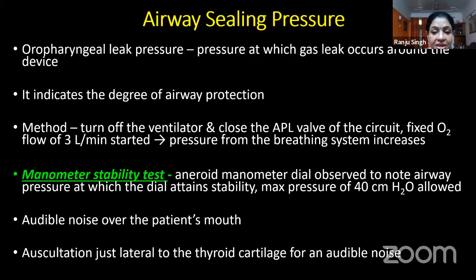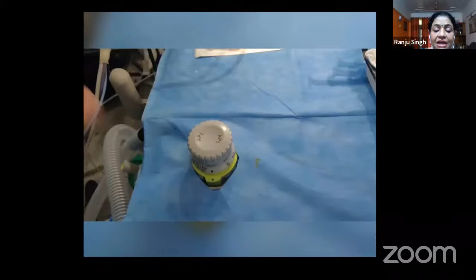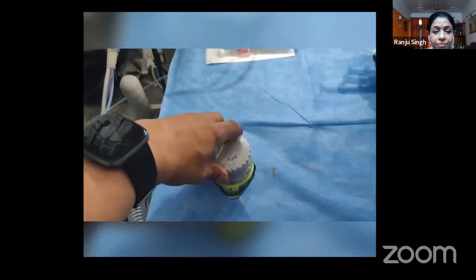This is a small video to show you how the oropharyngeal leak pressure is done. Every student who uses this must be able to describe the measurement of the oropharyngeal leak pressure in the exam. So you've put the patient on the ventilator, you switch off the ventilator for a little while, close the APL valve, set the patient on 100% oxygen at 3 liters per minute, and check for the airway pressures. Flow being increased to 3 liters, 100% oxygen.